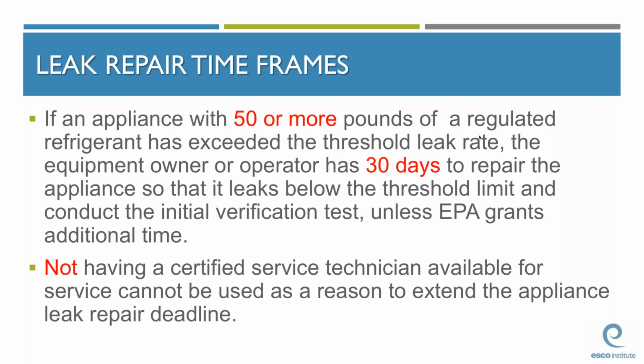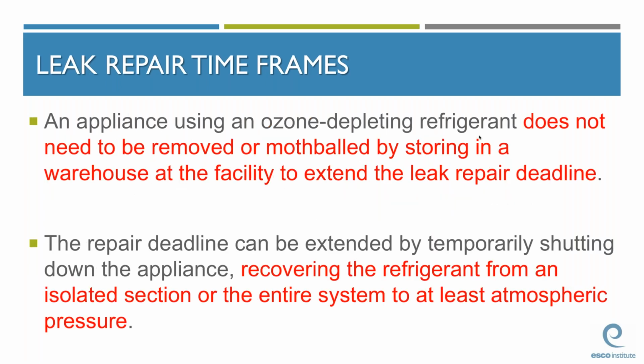Under certain conditions and on a case-by-case basis, the EPA can extend this 30-day repair requirement. Although there are a lot of reasons why they will extend, not having a certified technician available to perform the service cannot be used as a reason to extend the appliance leak repair deadline. A system that uses an ozone-depleting refrigerant does not need to be disassembled, removed, or mothballed to extend that leak rate repair deadline. The repair deadline can be extended if the system is temporarily shut down and the refrigerant is recovered from either the entire system or the leaking portion of the system to at least atmospheric pressure.